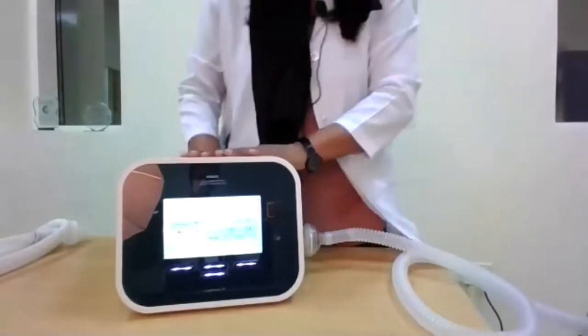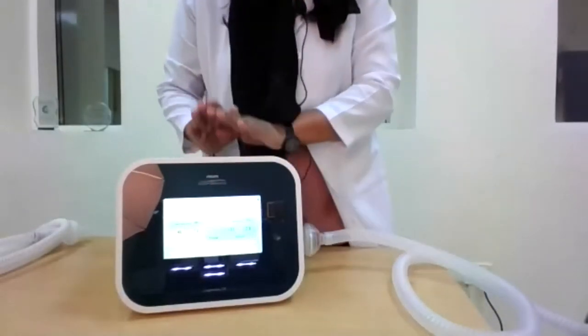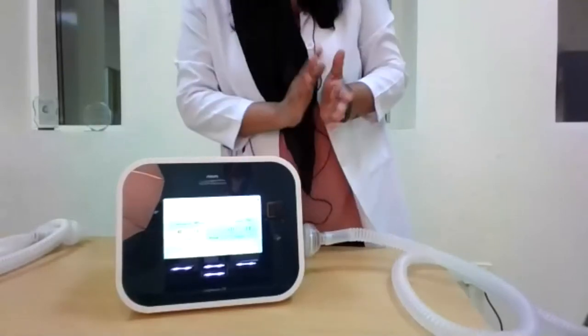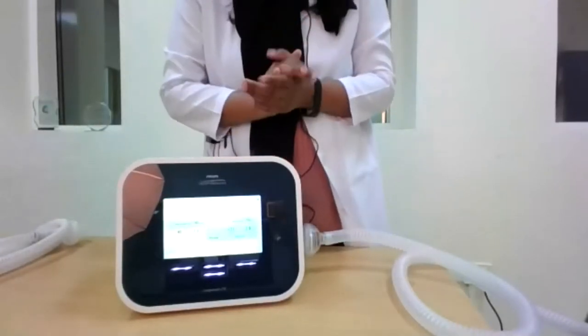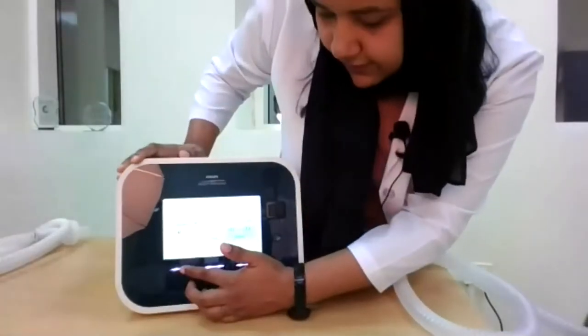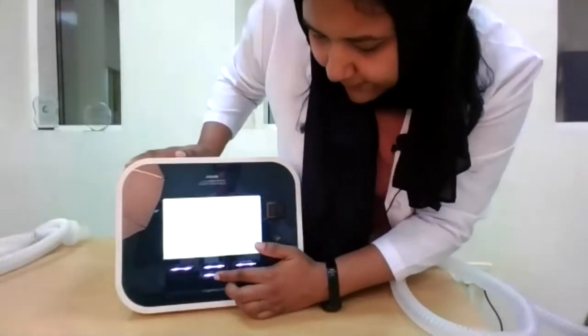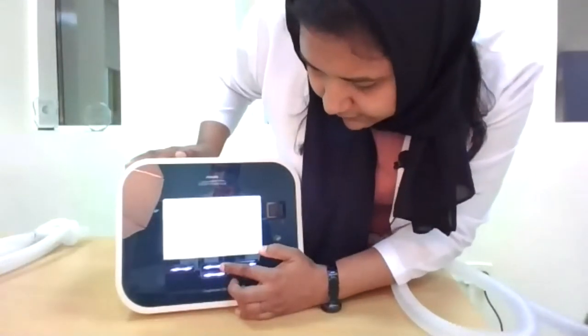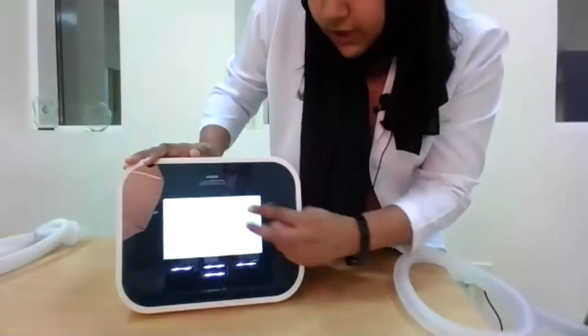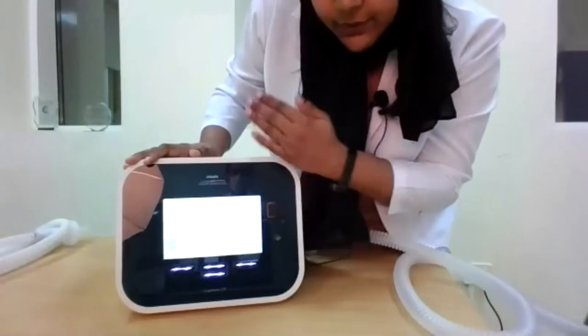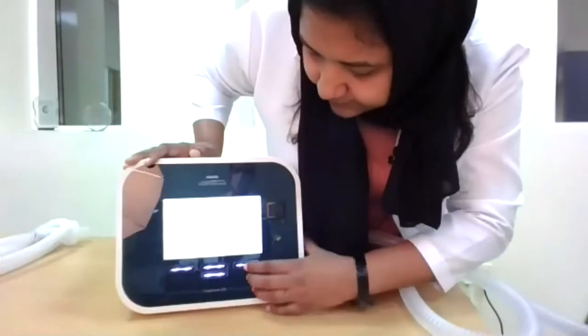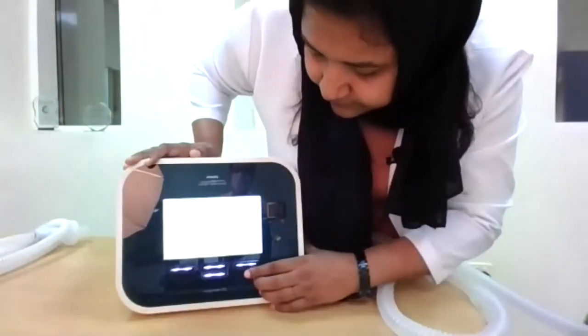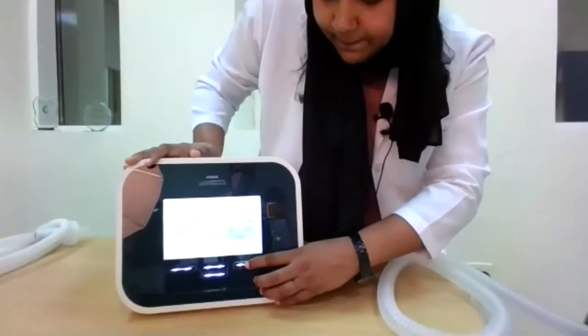Now, the next highlighted feature of this device is to provide oscillations along with the positive pressure as well as during the exhalation phase. To select the oscillations, go to the settings. You can select the options for oscillations. In this case, it has been enabled for both, which means oscillations will be provided during inhalation as well as during exhalation.